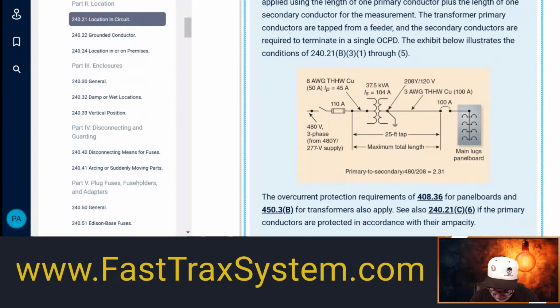And this is, let's work this out. So this is for 480. So we'll go 37,500 divided by 831.36. Okay. And let's see here. Oops. Okay. Oops. Hold on. I got my math backwards on that one. So, all right. And then of course, that's what we got. And then of course, we're dealing with the secondary, and let's see what the secondary would be. Primary protection here, you see it says 45 amps. And how do we get that? Well, what we did was we took this 37,500, right?